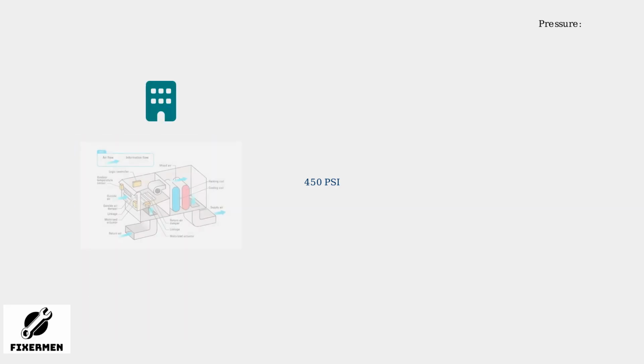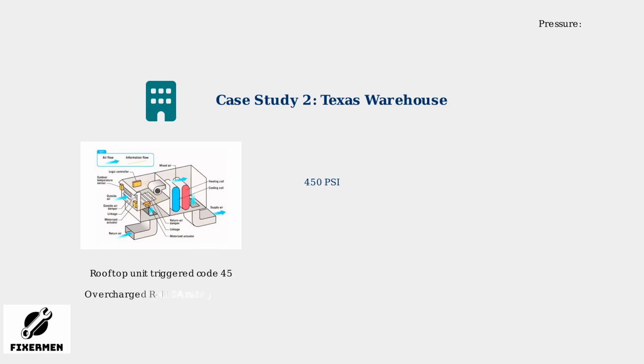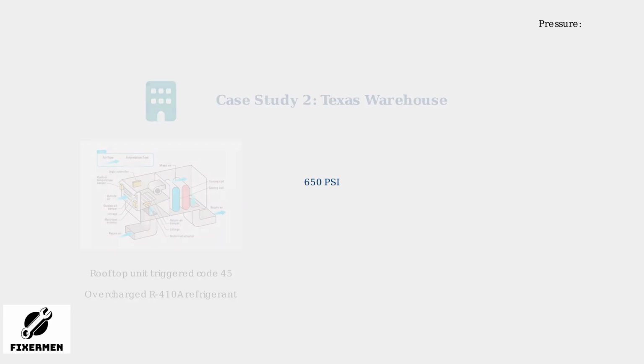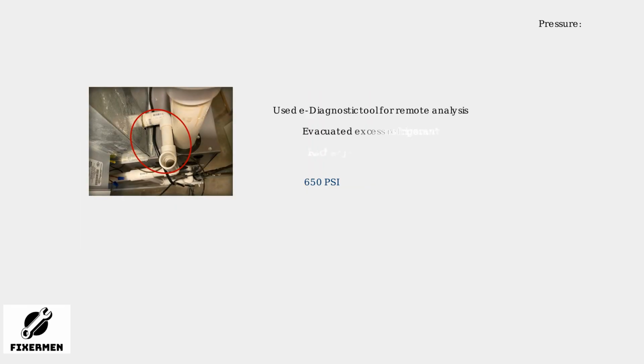Our second case study involves a commercial rooftop unit in a Texas warehouse that triggered code 45 due to overcharged refrigerant. The system was using R410A refrigerant. An excessive charge caused pressures to spike above safe limits during operation. Using Carrier's e-diagnostic tool for remote analysis, technicians identified the overcharge through pressure sensor data. The fix involved evacuating the excess refrigerant and recharging to the manufacturer's specifications. Downtime was reduced from 48 hours to just 4 hours, showcasing the value of digital diagnostics in commercial applications.